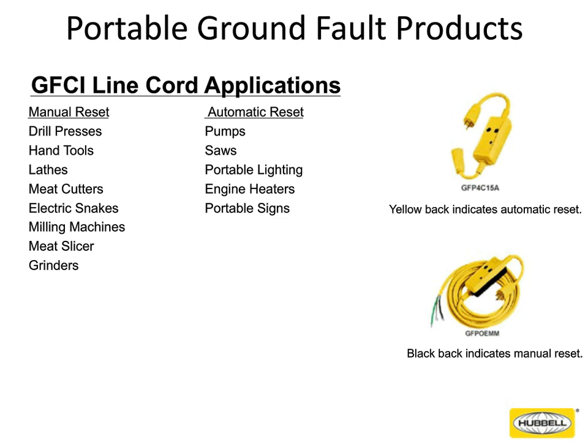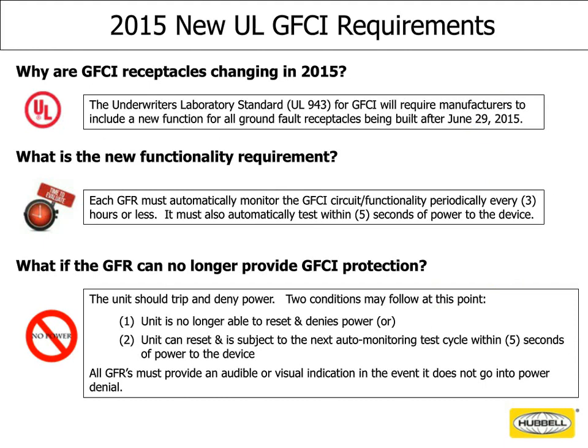Automatic reset units come in handy if you've got something plugged in to a sump pump and there's a power outage. When the power comes back on, if you have a piece of equipment that you want to come back on with the power, and you don't want somebody to physically have to be there to reset it, then an automatic reset is something you would want to use. We've had situations where people put portable ground faults in cell tower applications that are unmanned, and when that power comes back on, you want the GFI to automatically come back on. So that's where you're going to use an automatic reset: typically situations where you want the power to come back on regardless of whether there are any people available.